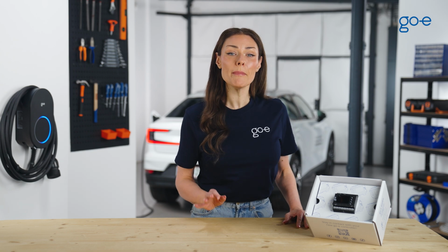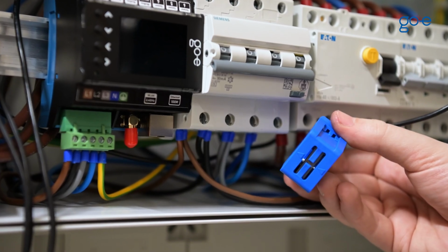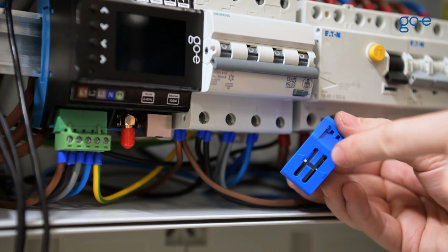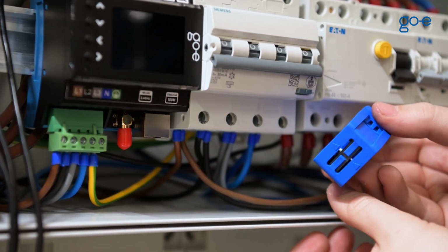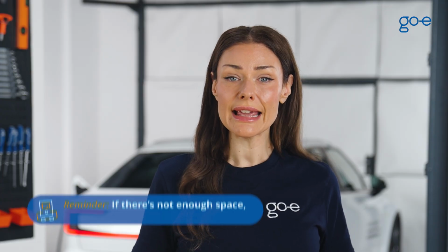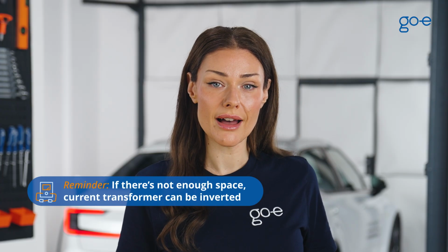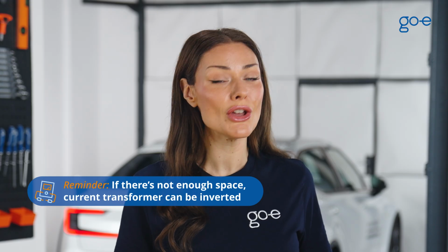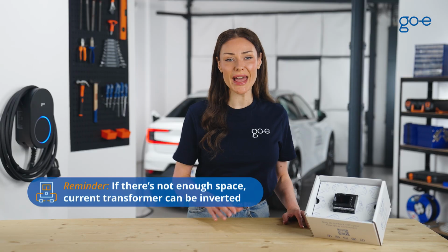For 3-phase devices that draw the same power across all phases, such as an AC inverter, measuring just one phase is usually sufficient. Again, make sure that the 2 arrows on the current transformer point in the correct direction of current flow. It's not possible to clip a single current transformer around several phases at once, even though that might seem convenient for something like an electric cooker. And once again, a quick reminder, if there's not enough space to install the current transformer in the right orientation, you can simply invert the sensor. We'll show you how to do that later.